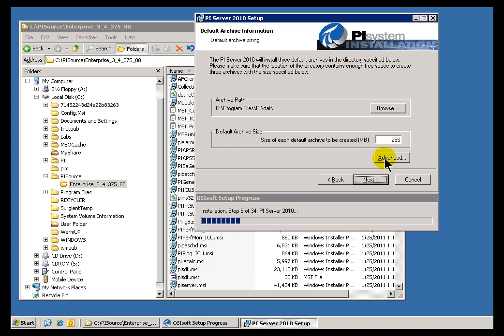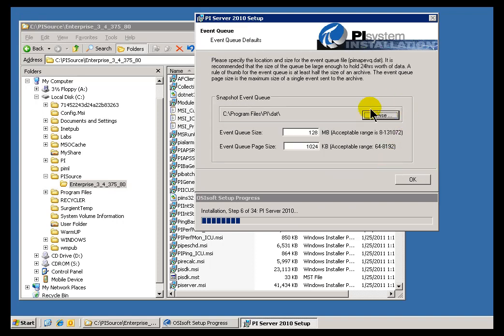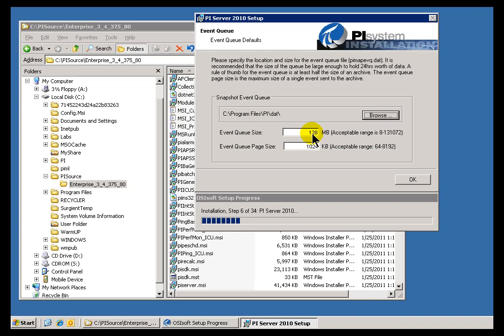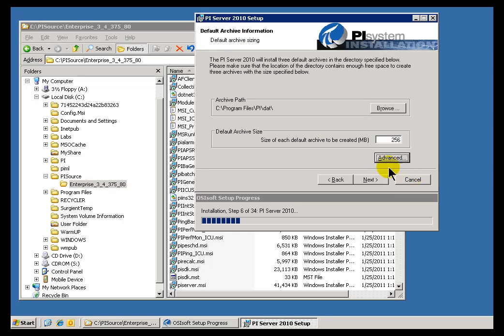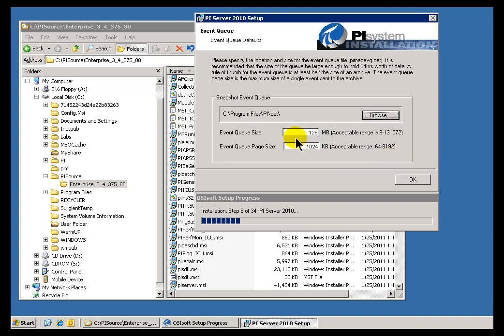Now next up is this Advanced Option. The Advanced Option gives you the choice of what you do for certain internal settings, the Event Queue Size and the Event Queue Page Size. What we're talking about here is the Event Queue is used in cases where the Archive is unavailable. We can buffer things temporarily in the Event Queue. Our recommendation is to make this half the size of the Archive. As you can see, that's what it is already. If I look at my Archive, it's 256 MB, so we've set this up at half that size.